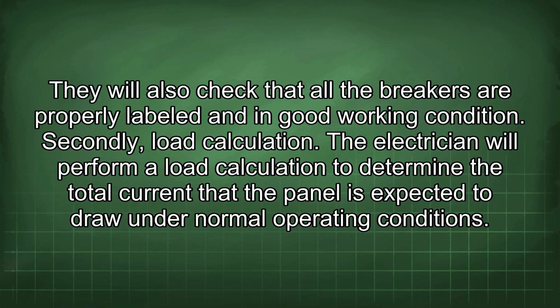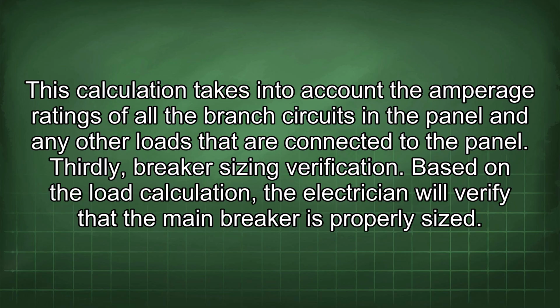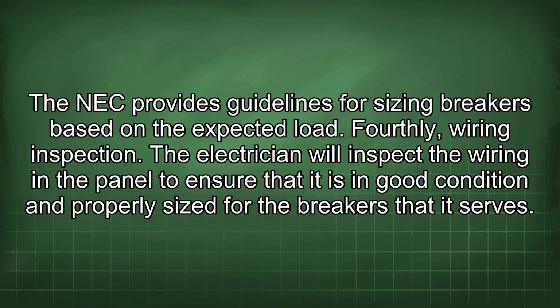Secondly, load calculation. The electrician will perform a load calculation to determine the total current that the panel is expected to draw under normal operating conditions. This calculation takes into account the amperage ratings of all the branch circuits in the panel and any other loads that are connected to the panel. Thirdly, breaker sizing verification. Based on the load calculation, the electrician will verify that the main breaker is properly sized. The NEC provides guidelines for sizing breakers based on the expected load.